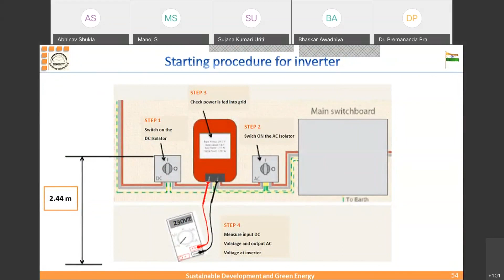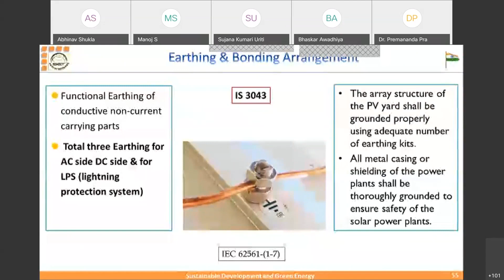Three types. One is AC earthing, where the AC side is your inverter and ACDB, and the DC side is your solar modules, structures, and the DCDB. So you have to connect all the components with two dedicated earthings, AC and DC, and there will be one dedicated earthing for the lightning arrestor. So they have to follow either IS 3043 or IEC 62561-1-7. This is very important. Standard, you will get the standard operating procedure in any PWD guideline or something. So a standard SOP is there for these earthings.